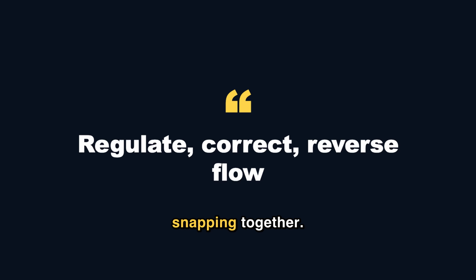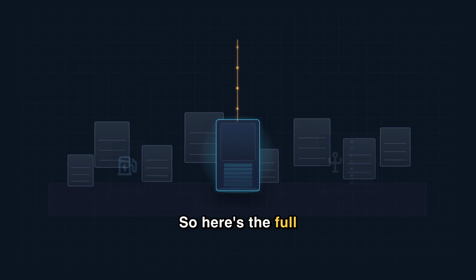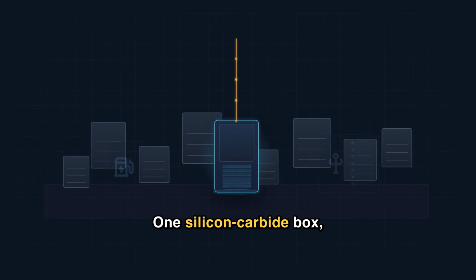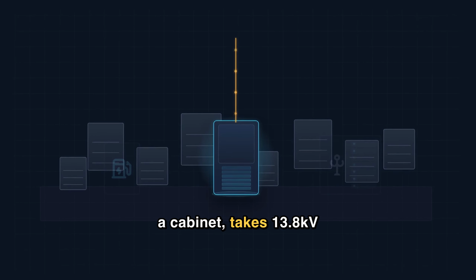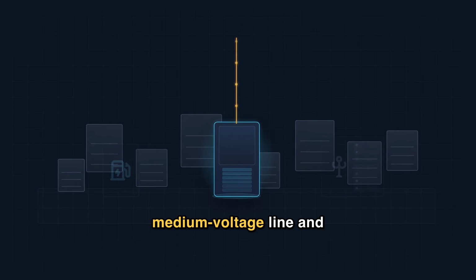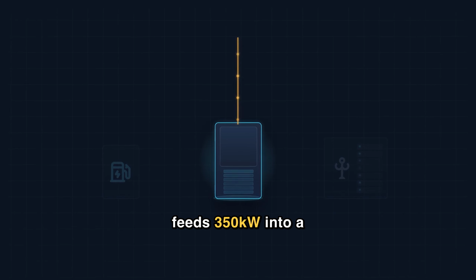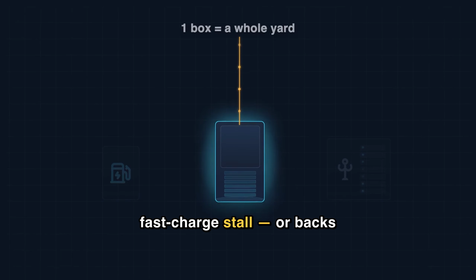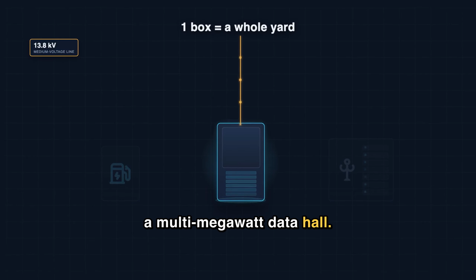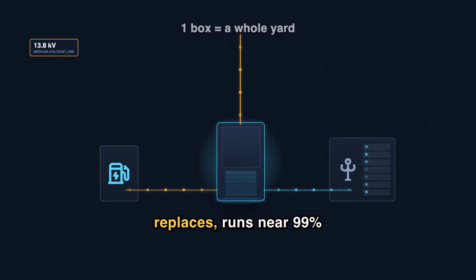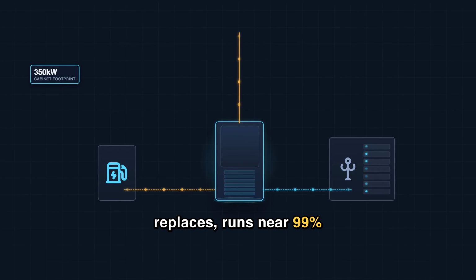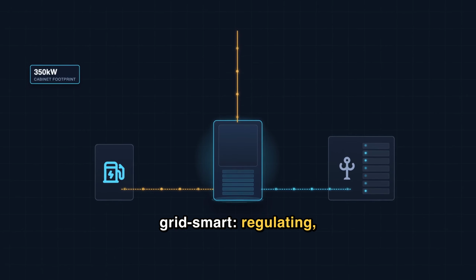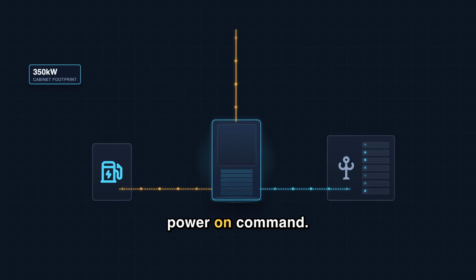So picture it all snapping together. Here's the full picture: one silicon carbide box, about the footprint of a cabinet, takes 13.8 kilovolts straight off the medium voltage line and feeds 350 kilowatts into a fast charge stall, or backs a multi-megawatt data hall. It's smaller than the room of iron it replaces, runs near 99% efficient, and it's grid smart, regulating, cleaning, and reversing power on command.